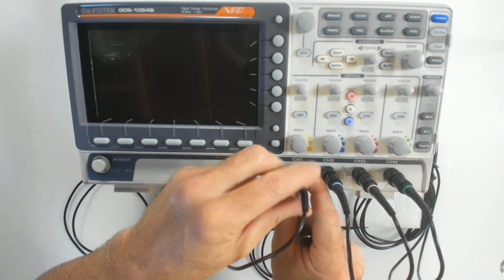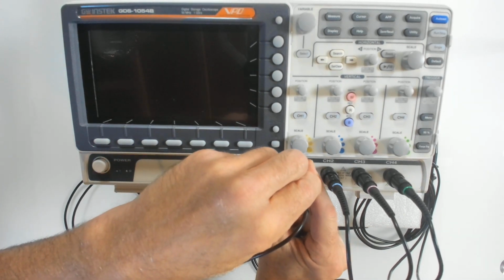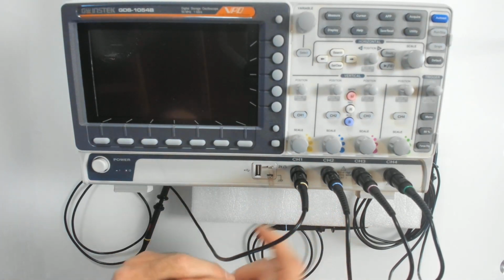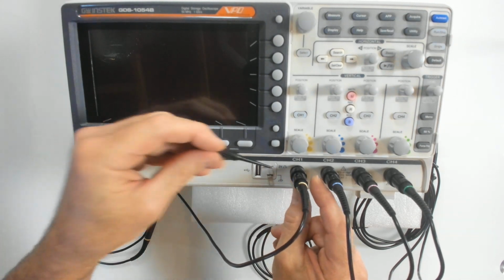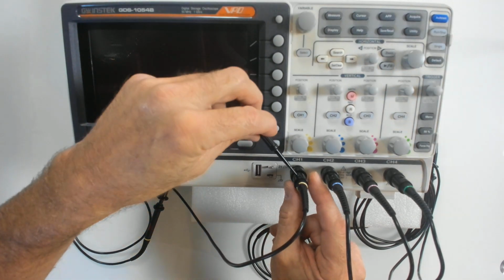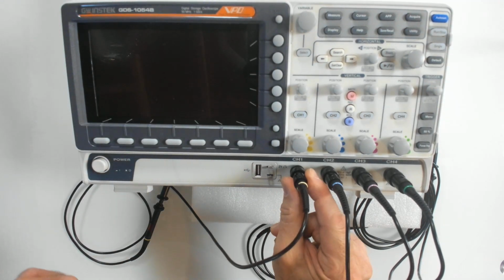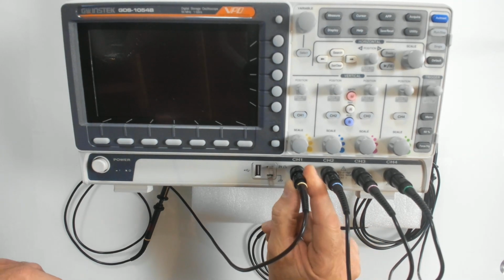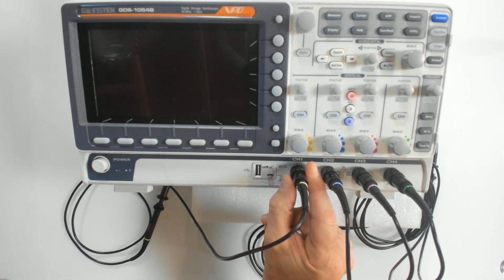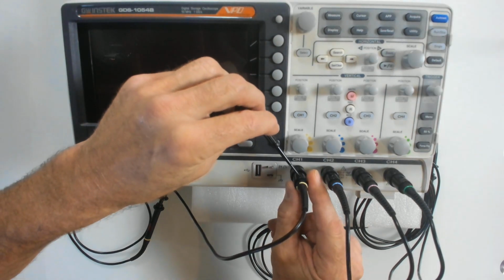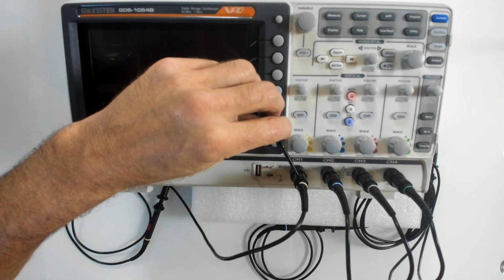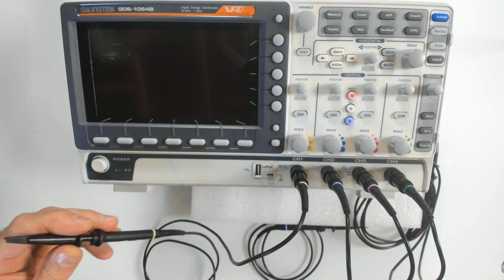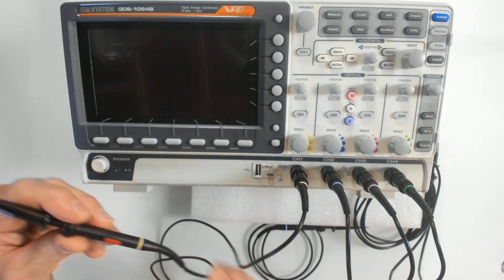When you attach the probe to the scope, you'll see first you have to get that BNC connector twist locked in place. And then, for example, if this adjustment hole where the trimmer cap is wasn't available, if it was facing down here at the bottom, you can rotate this barrel of this probe. Just be careful, all of this is fragile. You don't want to overdo things and break things. But you can always rotate that if you needed to, so that you have access to adjust it. And finally, at the other end of the probe, we have one more thing to look at, and then we'll actually do the whole probe setup with the scope.